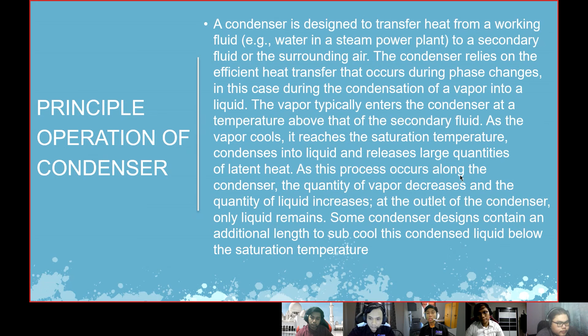As the vapor cools, it reaches the saturation temperature, condenses into liquid and releases large quantities of latent heat. As the process occurs along the condenser, the quantity of vapor decreases and the quantity of liquid increases. At the outlet of the condenser, only liquid remains. Some condenser designs contain an additional length to subcool this condensed liquid below the saturation temperature.